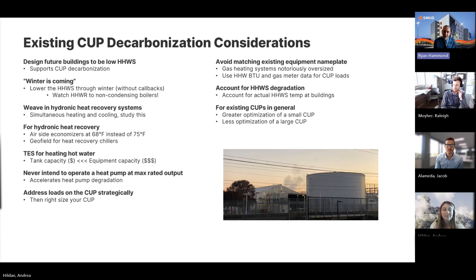The reason I mentioned that, and it was illustrated earlier, the lower heating hot water temps you get, the higher COPs you get, the more capacity you get out of your machine, the more relaxed your heat pumps will be, and we all want to be relaxed. You'll get extra life out of the machine. It's just awesome. But I do want to point out, watch the heating hot water return to your non-condensing boilers, because you'll give them a bad time otherwise, so you can coordinate with facilities on that.